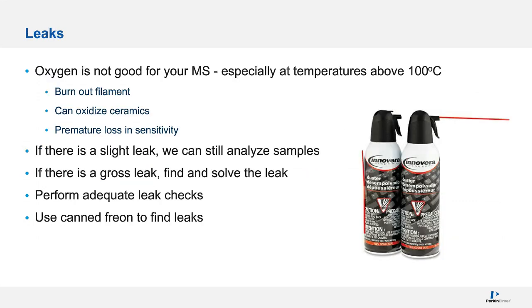A high level of oxygen from a small leak is not going to do anything, even a medium-sized leak. But if you don't see any carrier gas and all you see is air, that's a large leak. For finding leaks, Freon spray or dust off, whatever you have, is beautiful because it does a good job of finding even slight leaks in a system. One time I used methylene chloride to find a leak. That was a bad idea. We don't want to use a liquid to find a leak in a mass spec. I was a newbie. So the dust off works really good.